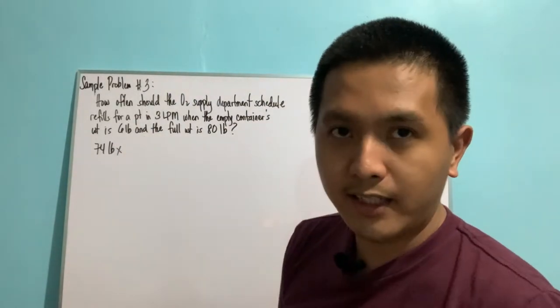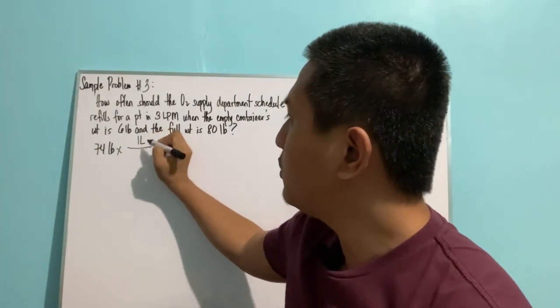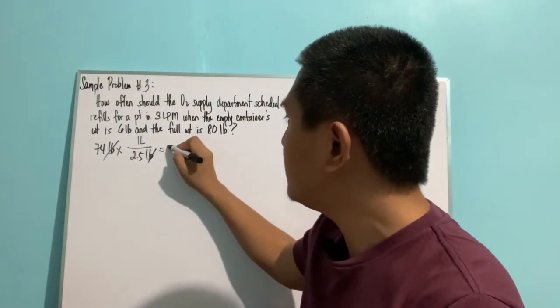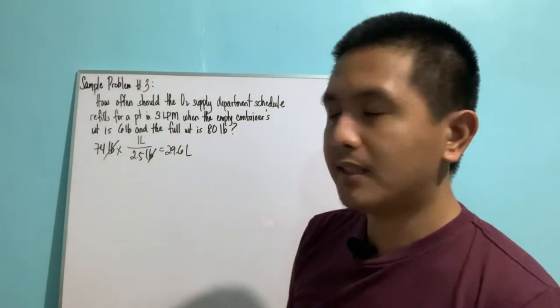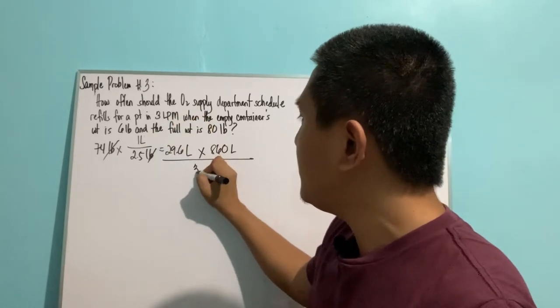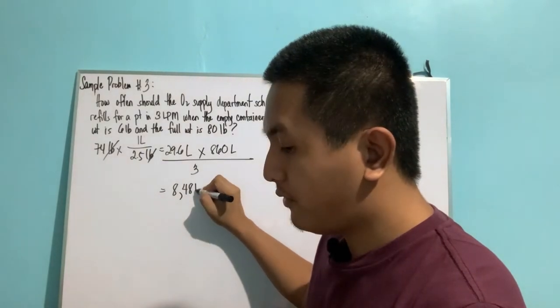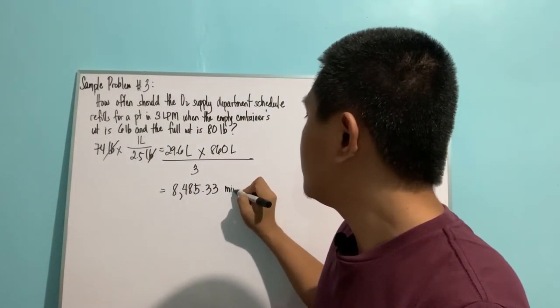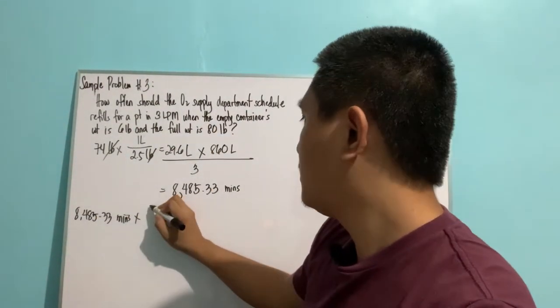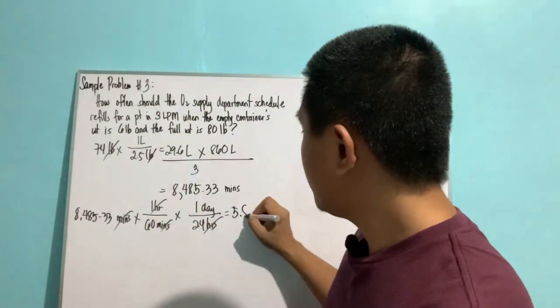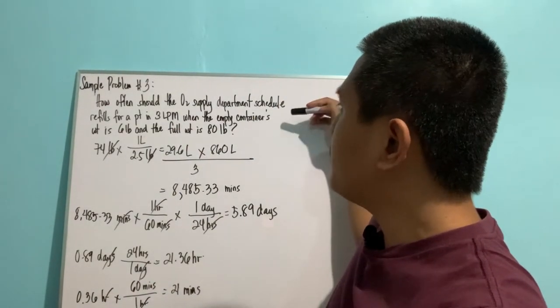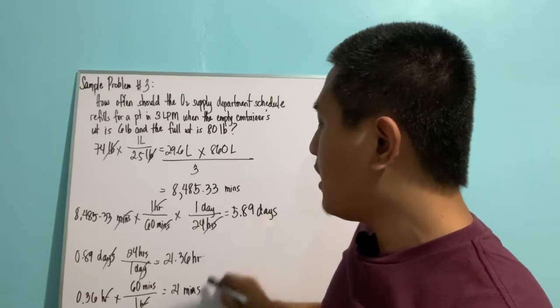We need to convert 74 pounds into liters of liquid oxygen. Divide 74 by 2.5 pounds per liter, giving 29.6 liters of liquid oxygen. Then convert to gaseous oxygen by multiplying by 860 and dividing by the flow rate of 3 LPM, giving 8,485.33 minutes. Converting to days, this liquid oxygen system would last for 5 days, 21 hours, and 21 minutes.